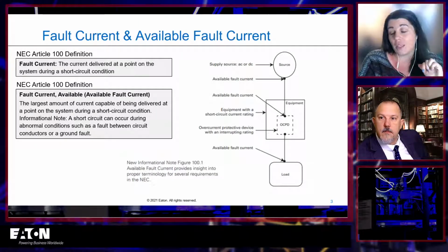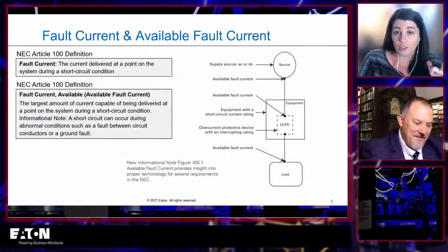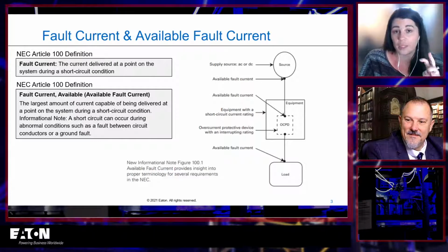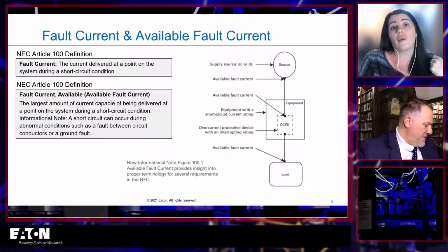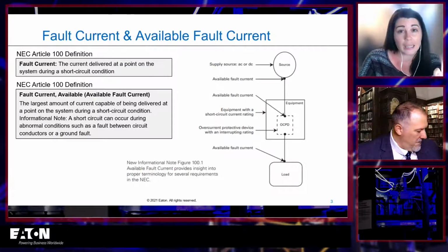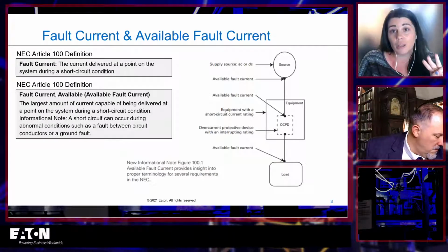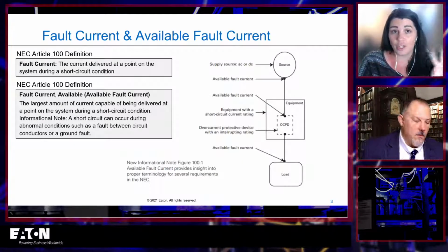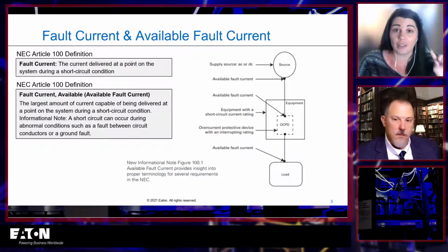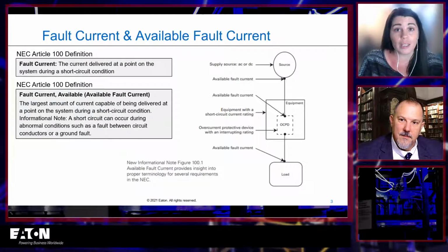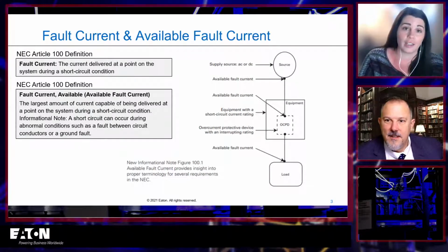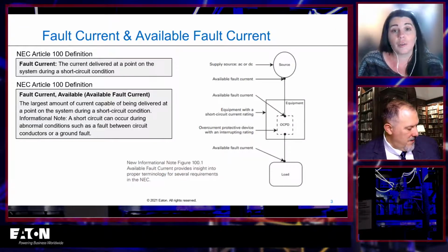So again, that could be any type of short circuit. It could be a ground fault. It could be a line to line. But the available fault current is going to be a three-phase fault. If I have a three-phase system, the line to line to line fault will be the available fault current. That's going to be the greatest amount of current we can see.